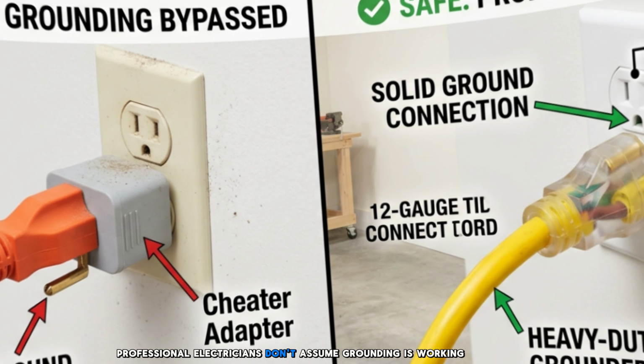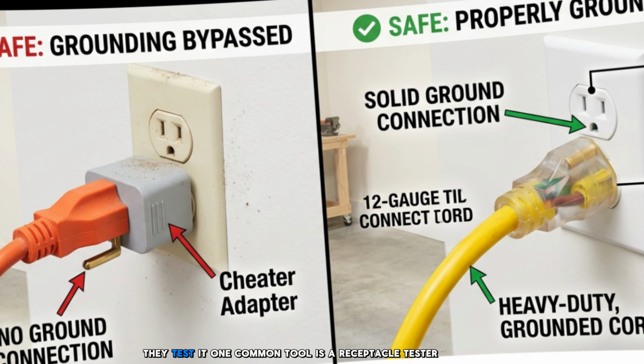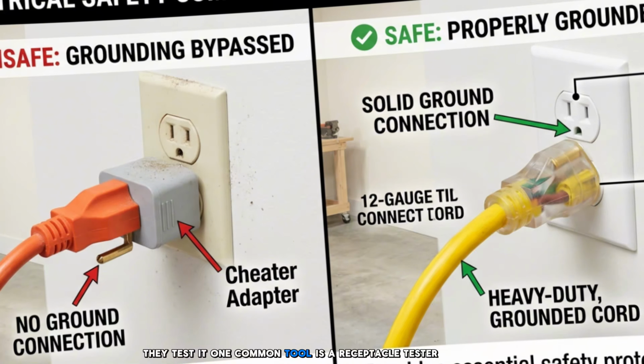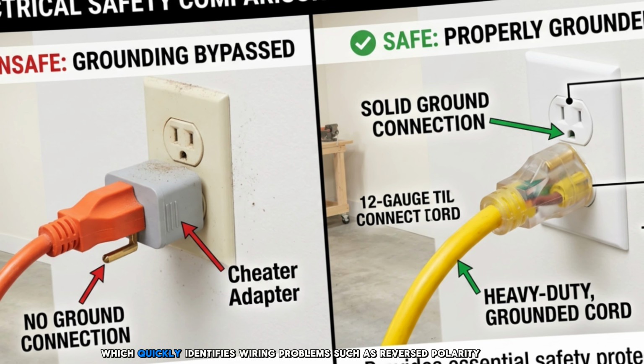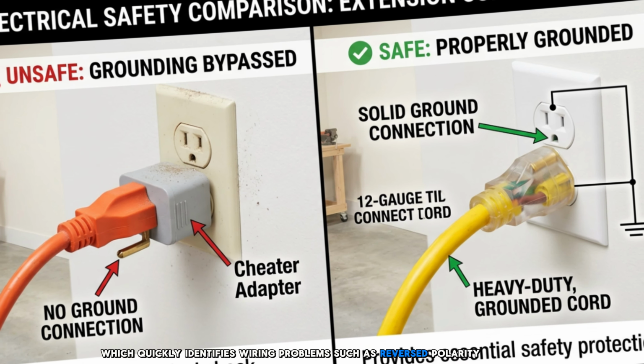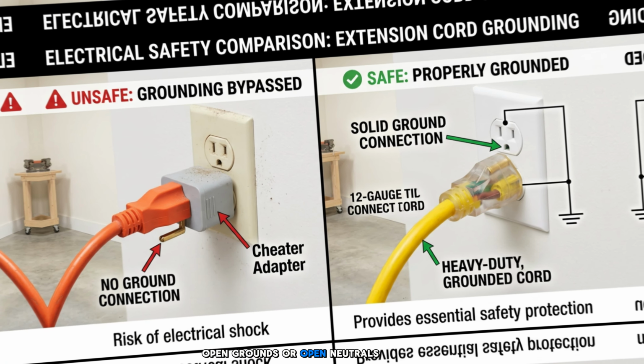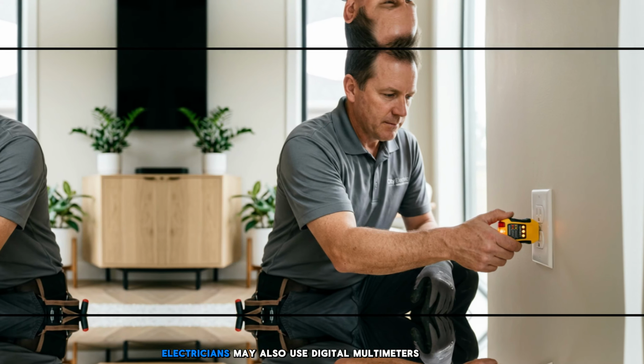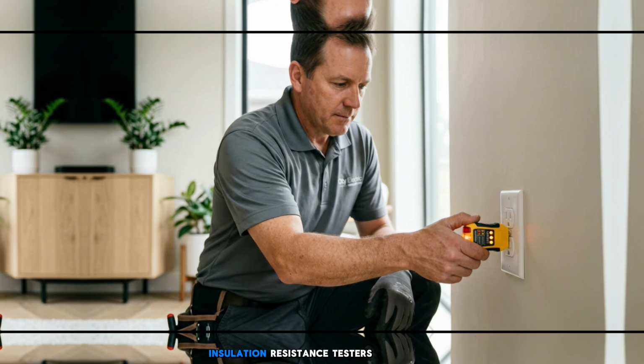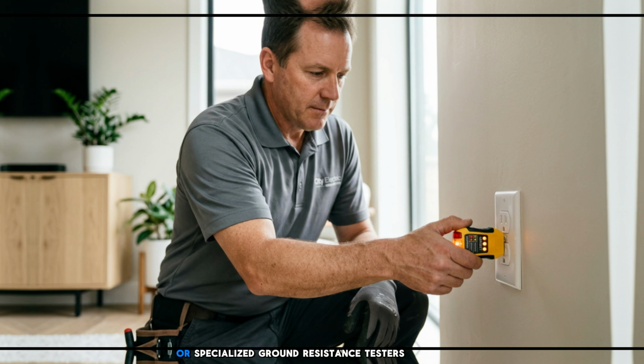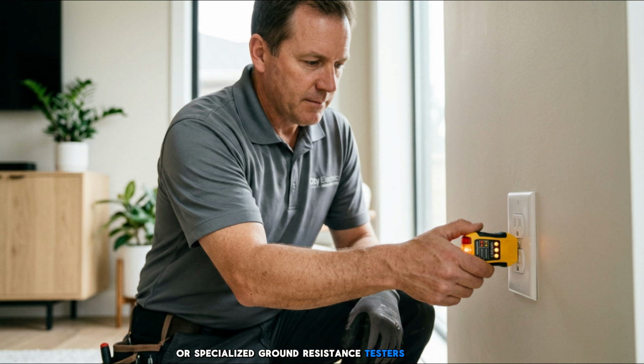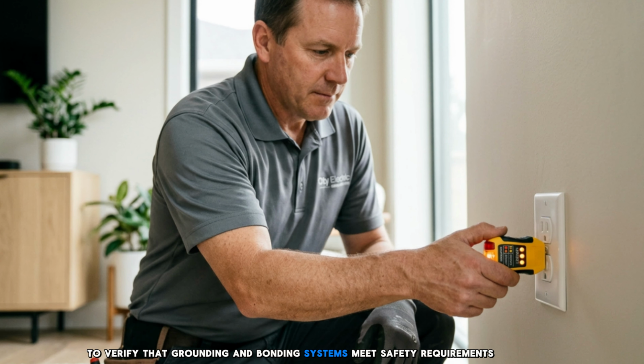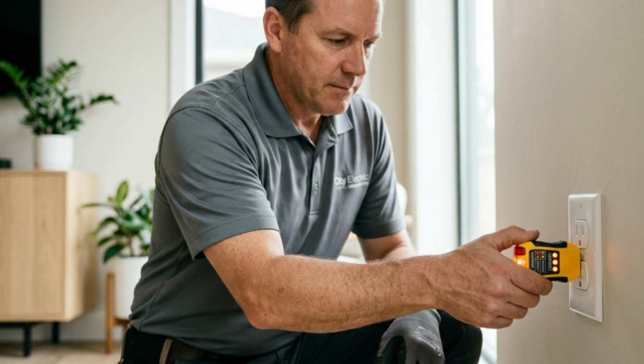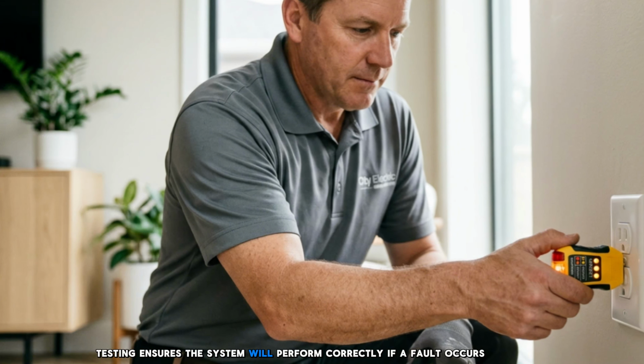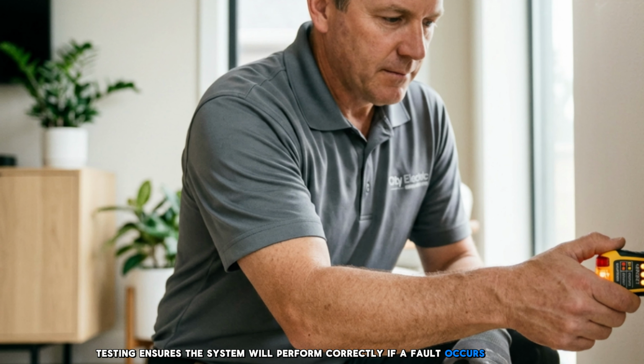Professional electricians don't assume grounding is working, they test it. One common tool is a receptacle tester, which quickly identifies wiring problems such as reversed polarity, open grounds, or open neutrals. Electricians may also use digital multimeters, insulation resistance testers, or specialized ground resistance testers to verify that grounding and bonding systems meet safety requirements. Testing ensures the system will perform correctly if a fault occurs.